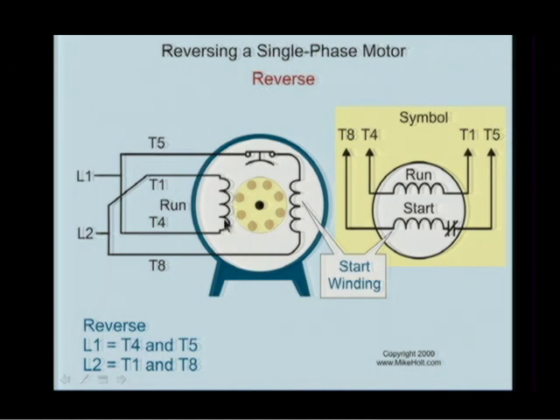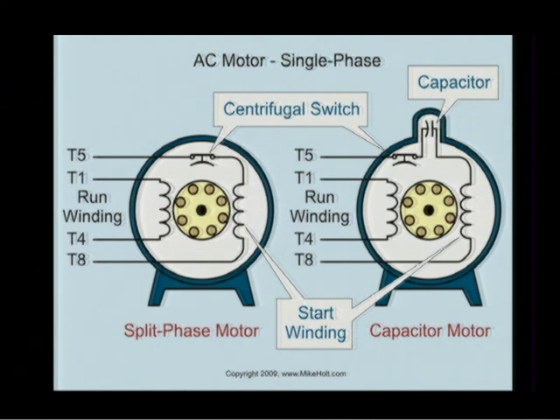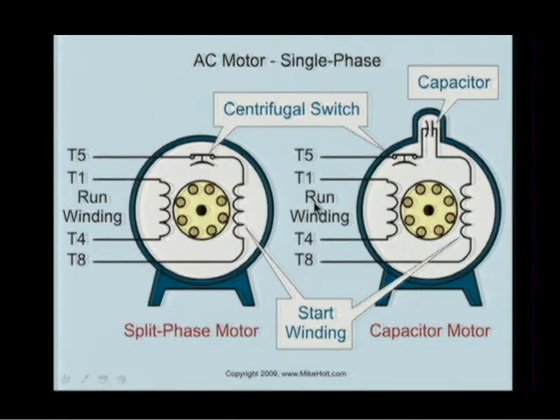It's going to cause the motor then to run in the reverse direction. Usually on the nameplate, the ones that tell you to switch are the start windings, so you know which one it is. We've just done it the opposite way here, but that's fine. It works as well. Well, then I guess let's just change this in the book. You say it's usually done with the start windings? Usually it's done with the start winding on the nameplate. In reality, you can switch either one of them. All right, we'll just change these all to start then in the textbook.